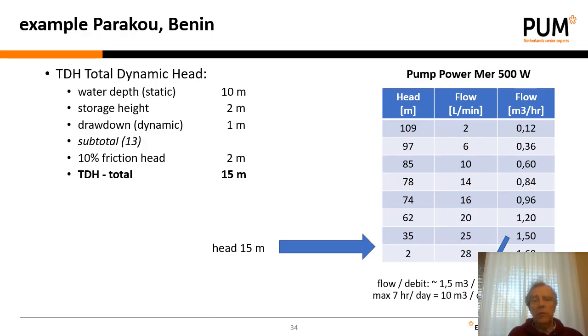Now, for the total dynamic head, the water depth was 10 meters. Storage height is 2 meters up, and the drawdown was 1 meter. As we discussed earlier, there's a 10% friction head we need to consider. So the total dynamic head that we have to anticipate is 15 meters. And in the table, you can see that we more or less have to look at a flow of about 1.5 cubic meters per hour. And it will be a little bit higher because our total dynamic head is of course lower than 35 meters, but this is a realistic number then.